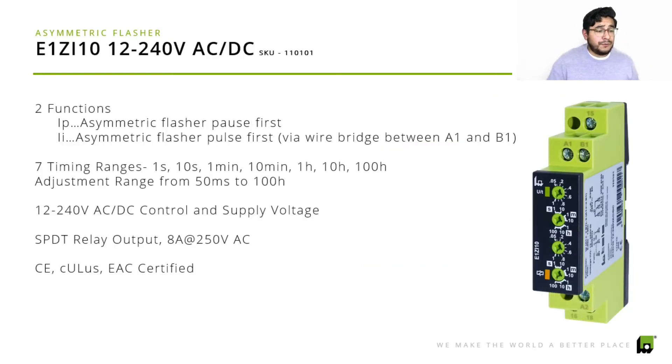The E1 ZI 10 is 12 to 240 volts AC/DC. You can see the wire bridge between A1 and B1. The two functions available on this product are: the asymmetric flash-pause-first, which is function IP, and function II, the asymmetric flasher-pulse-first. It offers seven time ranges from one second up to 100 hours, with adjustment ranges from 50 milliseconds to 100 hours — which is really great. You don't have to worry about readjusting it; that's such a long range, up to 100 hours. Supply and control voltage is 12 to 240 volts AC/DC, with a single-pole double-throw relay output.